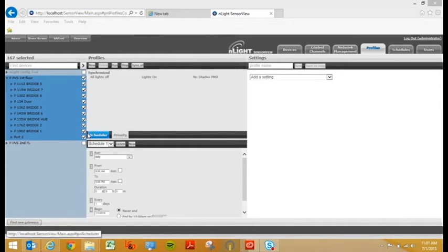Once our devices are selected, we can set our schedule by changing the inputs underneath Scheduler in the middle of our page. Here you can schedule the exact date, hour, or minute for any setting or control mode. You can also add astronomical start and end dates and set daily, weekly, monthly, or yearly recurrences. The drop-down menus provide options for more detailed patterns.